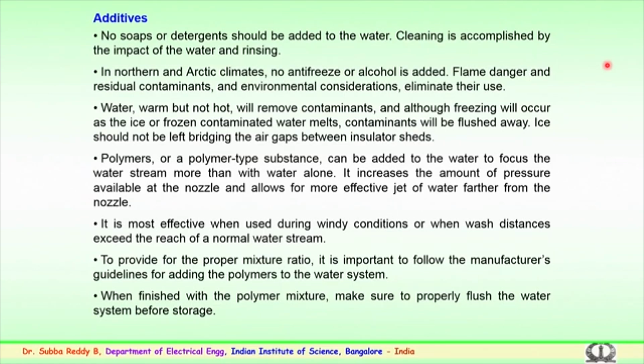This generally increases the amount of pressure available at the nozzle and allows for a more effective jet of water farther from the nozzles. Some substances related to polymers can also be used. They are most effective particularly during windy or high windy situations, or when wash distances exceed the reach of a normal water stream. In some cases it is difficult to go near the prescribed distances. In such cases polymers or polymer type substances are used for effective cleaning, which also helps in windy or high windy conditions.